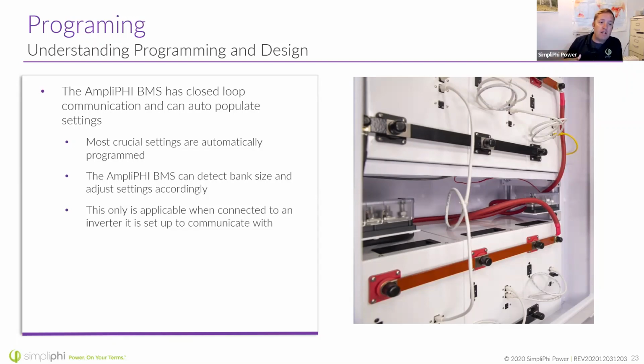What I should mention is our SimpliPhi batteries are only compatible with pieces of equipment that are able to talk to it. So currently, the Sol-Ark 5K, 8K, 12K, SMA Sunny Island, and our new SimpliPhi Briggs and Stratton inverter are able to communicate. If you have other inverters that have comms capability we're not working with currently, we're always trying to expand to bring that capability there.